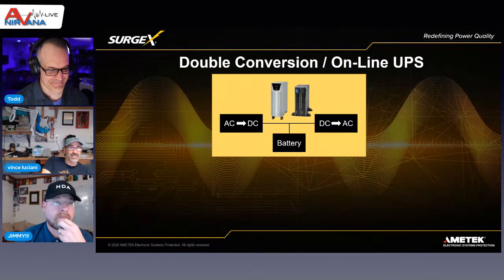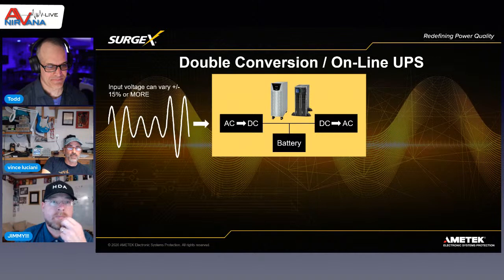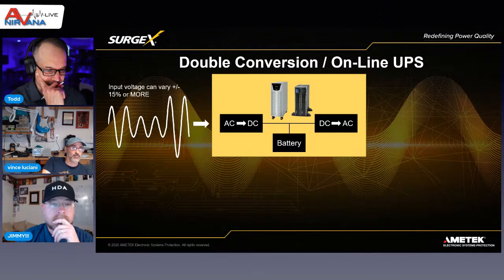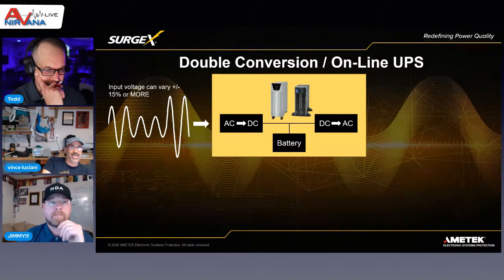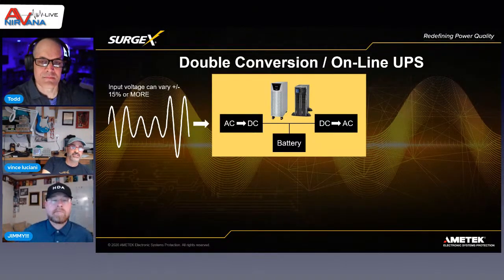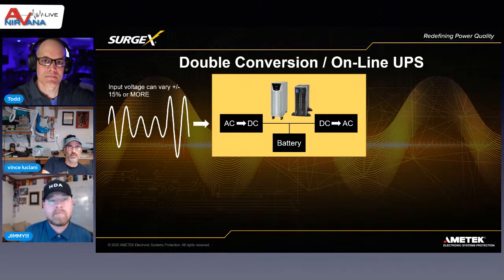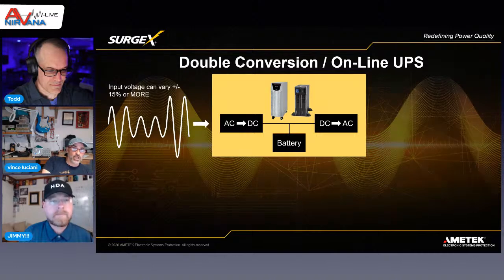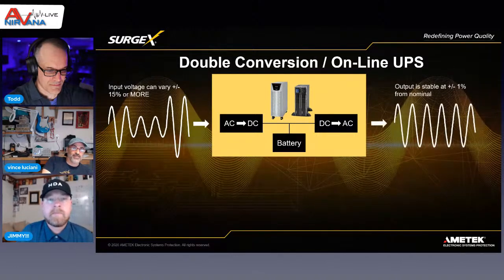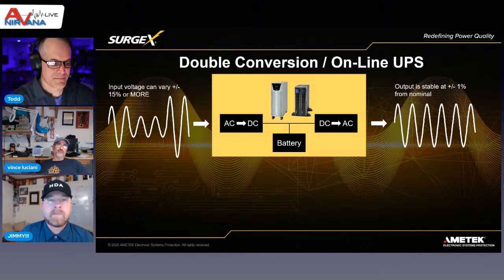What it does is take the incoming AC, which can vary plus or minus 15% or more—we have some models that can handle even a 30% deviation in voltage level. The AC gets turned into DC to charge the batteries, but it's also powering the DC to AC circuit full time. So these double conversion online UPSs are actually acting as voltage regulators.